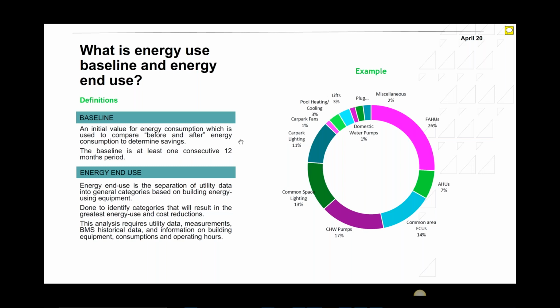So almost 60% voted that it's district cooling, which is the right answer. Why is that? If you look at the end use analysis, you can see there are no chillers, but I can see chilled water pumps, so there are pumps pumping chilled water within the building. It cannot be not cooled because I have fan coils and air handling units. It's not going to be air-cooled chillers because I don't see any chillers here on the end use analysis. So the only answer could be district cooling.